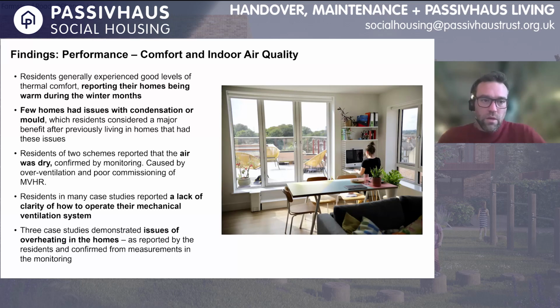In 2 of the schemes, residents said the air was dry, confirmed by monitoring - humidity levels below 40% in some instances, generally caused by overventilation and poor commissioning of the MVHR. So it's a combination of the product possibly, but also the length of ductwork - a design issue, and then the commissioning at the end not being balanced or done properly.